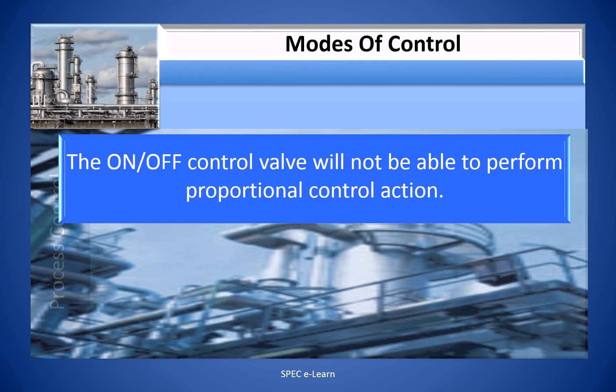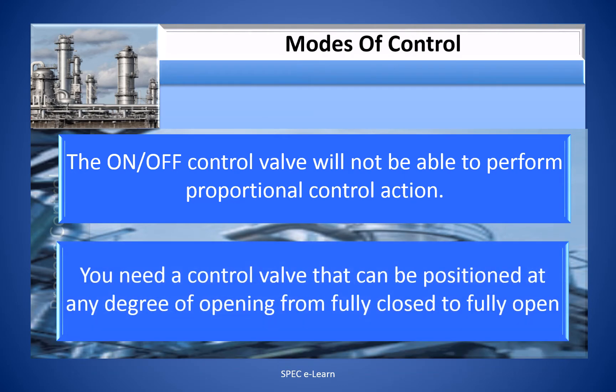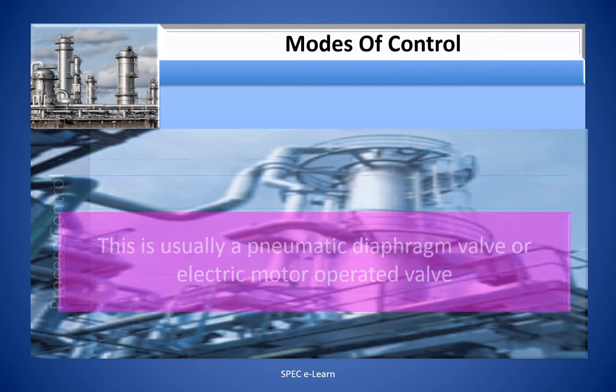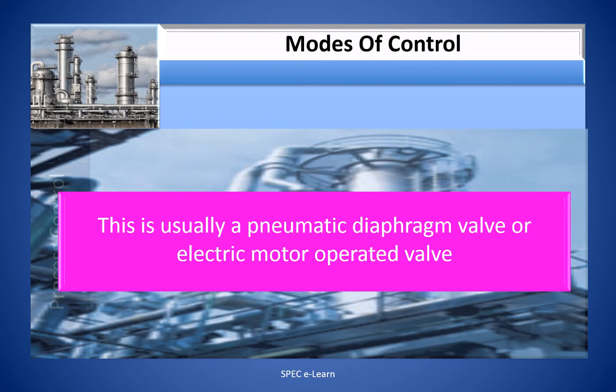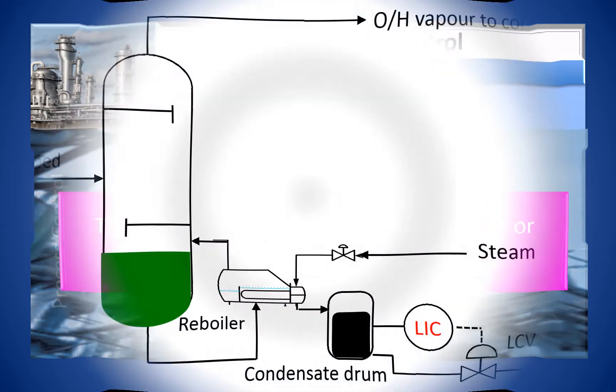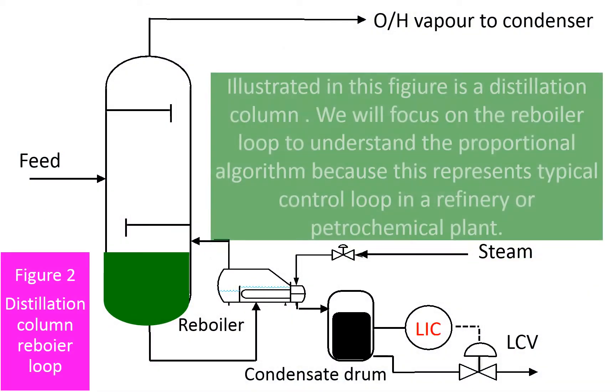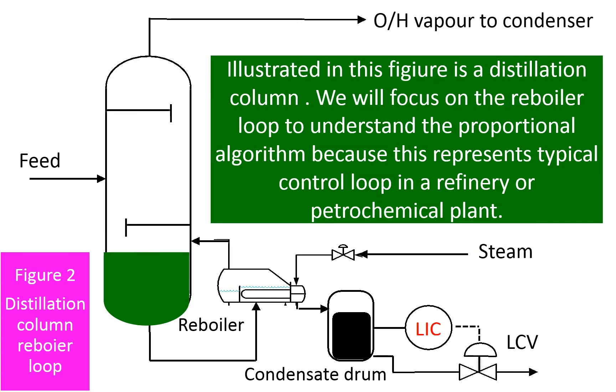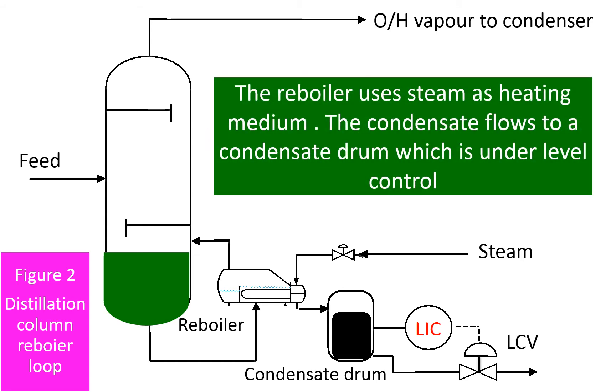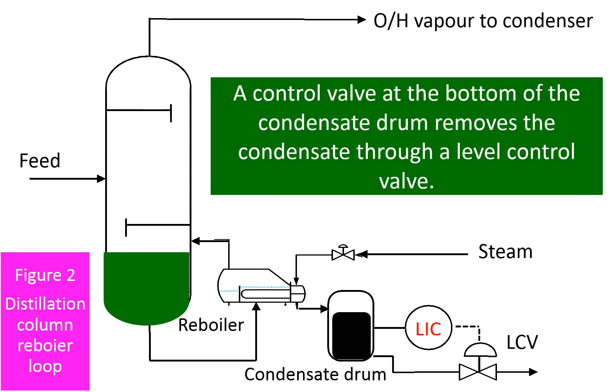The on-off control valve will not be able to perform proportional control action. You need a control valve that can be positioned at any degree of opening from fully closed to fully open — usually a pneumatic diaphragm valve or electric motor operated valve. Illustrated here is a distillation column. We will focus on the reboiler loop to understand the proportional algorithm, as this represents a typical control loop in a refinery or petrochemical plant. The reboiler uses steam as a heating medium, and condensate flows to a condensate drum under level control, with a control valve at the bottom removing condensate.